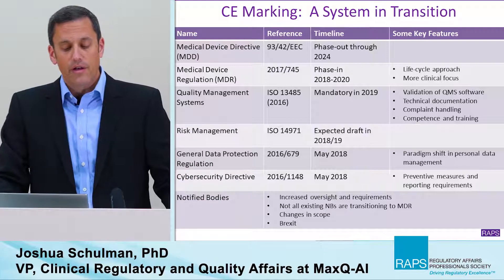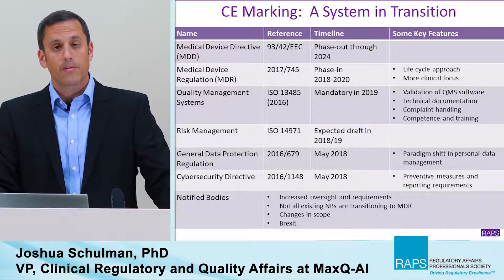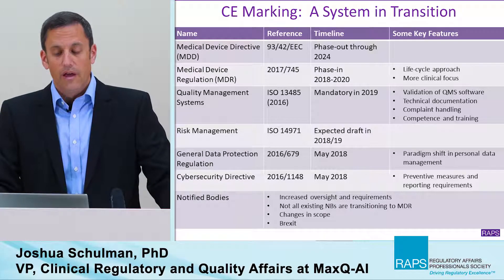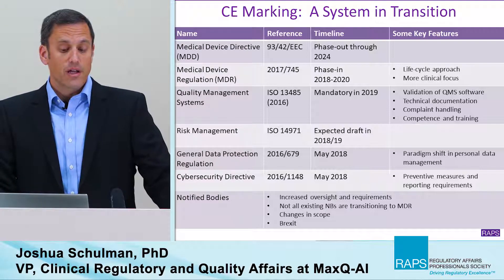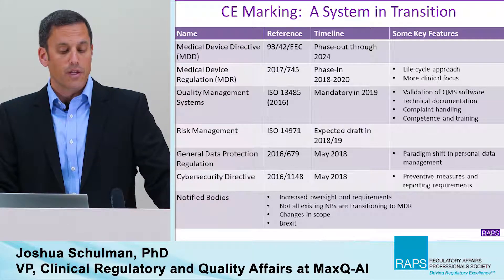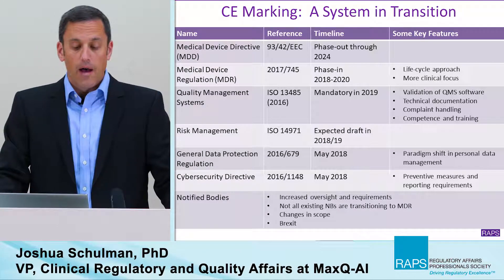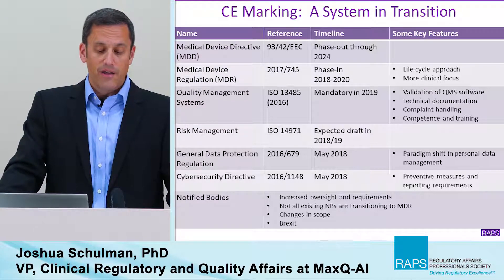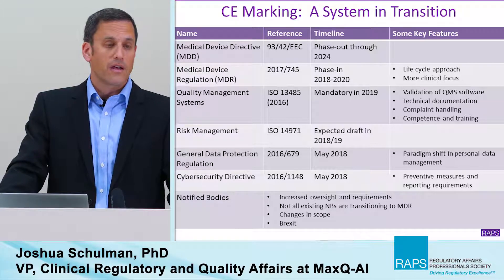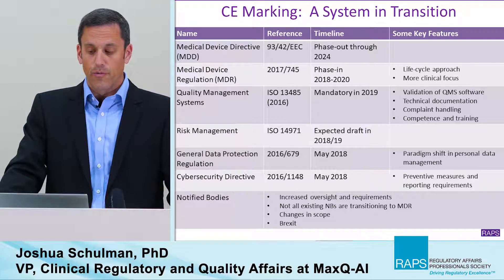Finally, the notified body space itself has really changed over the last few years. Following the PIP scandal a number of years ago, there's been increased oversight of notified bodies. In addition, as the space moves toward the MDR, the Medical Device Regulation, not all of the existing notified bodies are transitioning to MDR. Furthermore, some of the ones that are transitioning to MDR are changing in scope. And finally, there are a number of notified bodies that are located in the UK who may or may not continue their activities following Brexit.